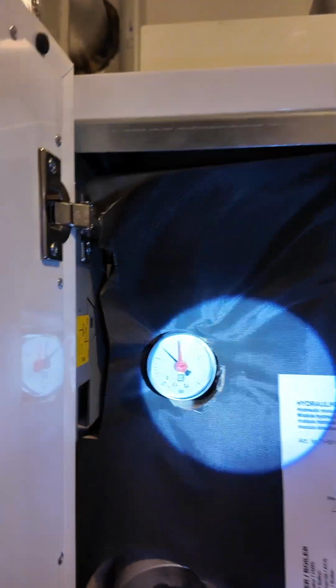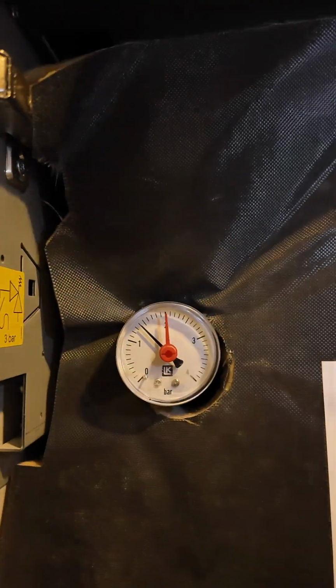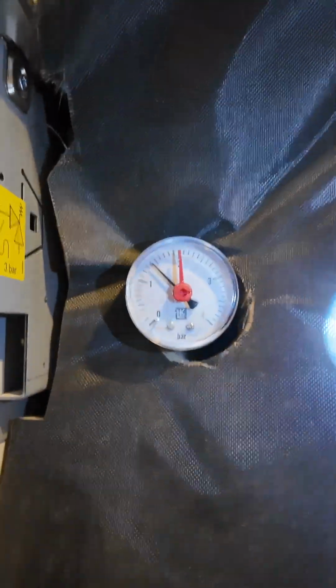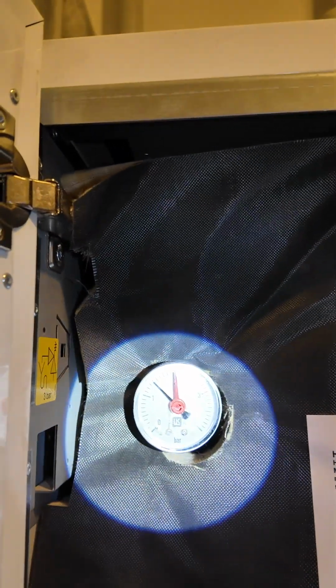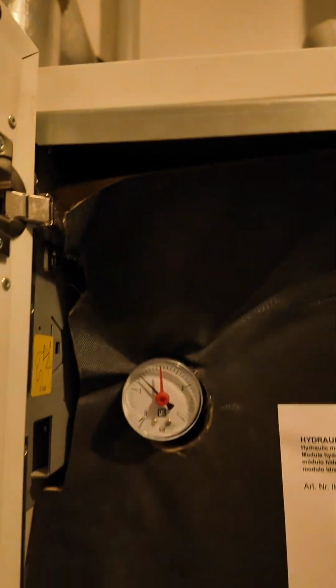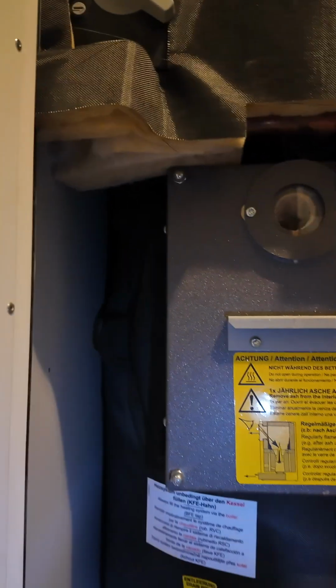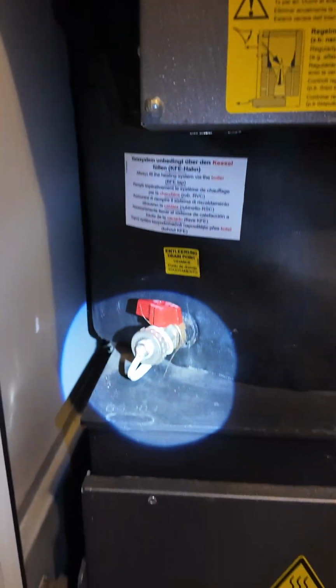And just in case you didn't know, the warm water flows through tubes here in the bottom underneath your flooring. Finally, another thing to mention is here is the bar reading of our heating system. You can see we're at about 1.4 bar and the set point would be 2 bars normally. And where you fill it is down here. That's where you put water into the Heizwasser. And where you gotta fill it from is this here.